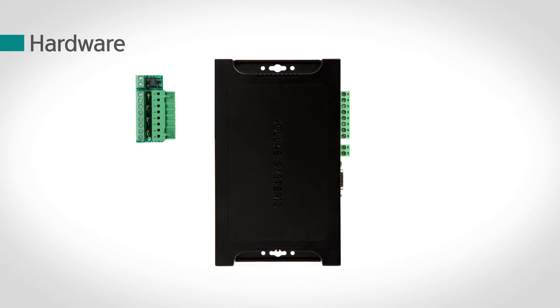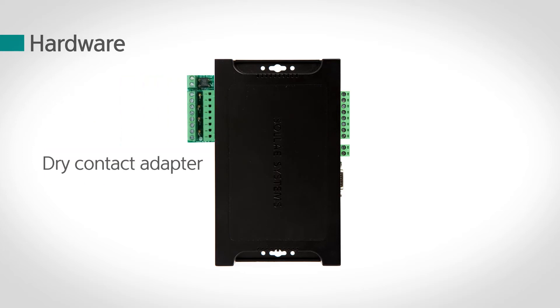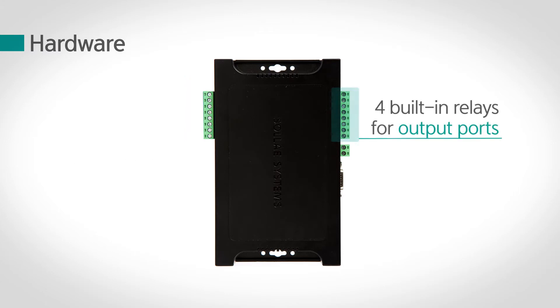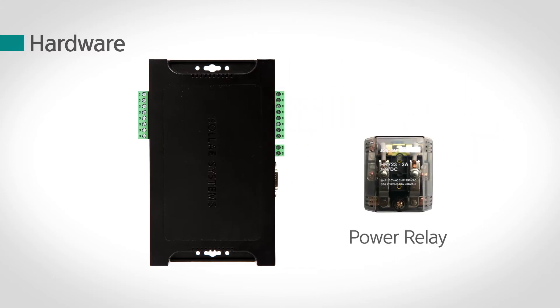Sending signals with a switch or relay requires an additional dry contact adapter. There are 4 output ports with built-in relays. The maximum allowable relay rating is DC 28V 5A at its peak. An additional power relay is required for AC control.